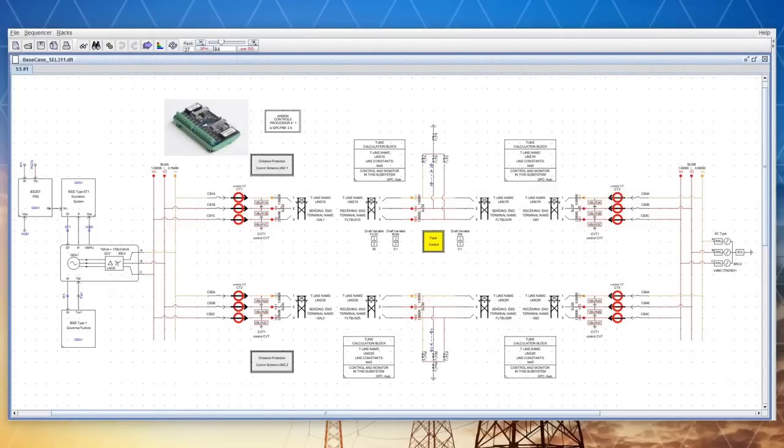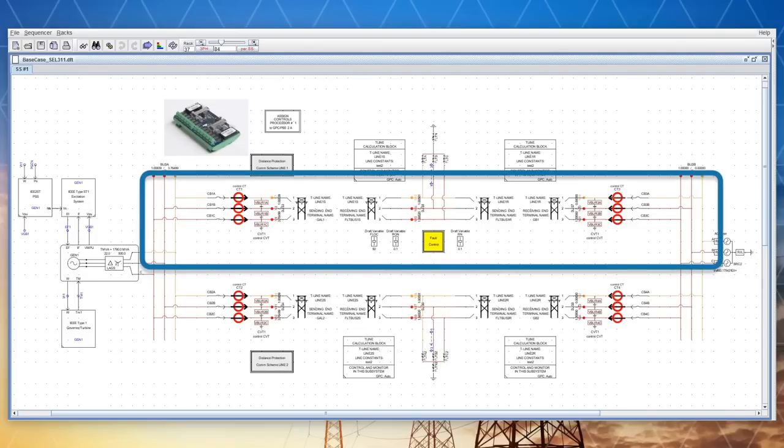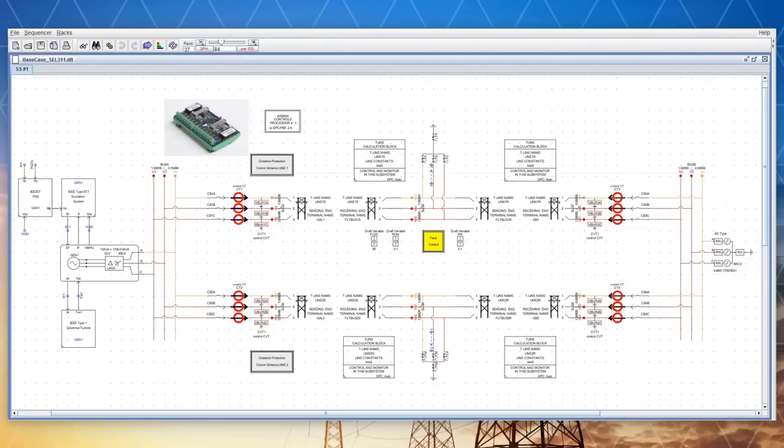A simulation case has been developed in the draft module of RSCAD for testing the physical distance protection relay. The case includes a transmission line containing a fault branch, the position and resistance of which can be defined and varied by the user from the runtime module.